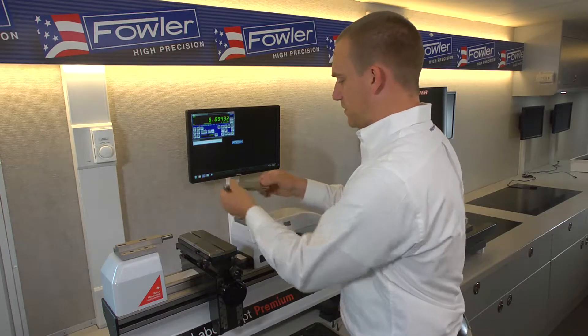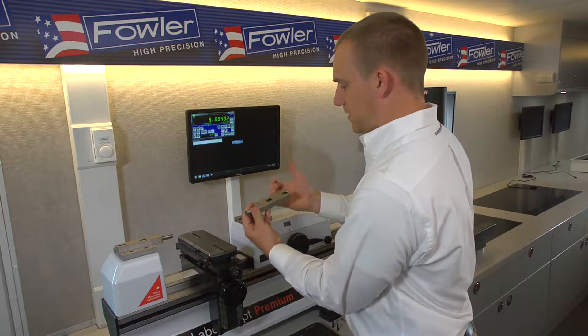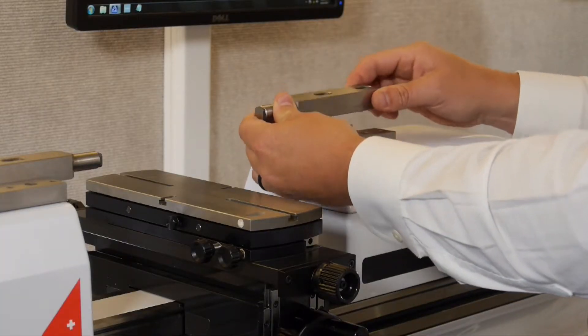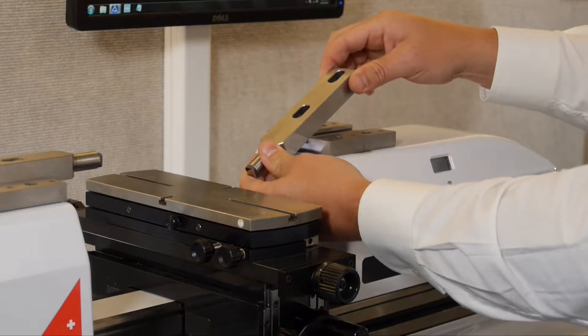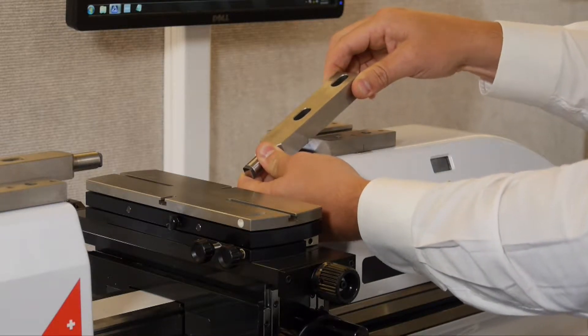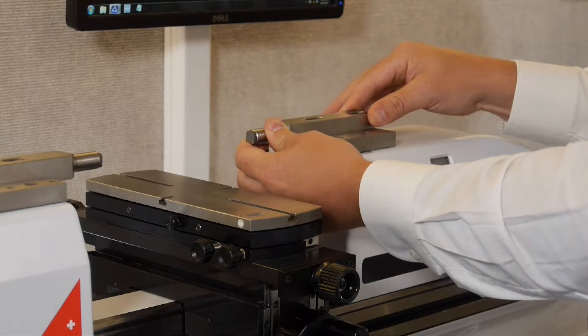A note about these: the fit to the sides and bottom is very, very tight. So you never want to just try to drop the anvil back in. It's easy to get it wedged. A good technique is to go from the corner where you can rock the anvil until it hits bottom and then slot it right into place.